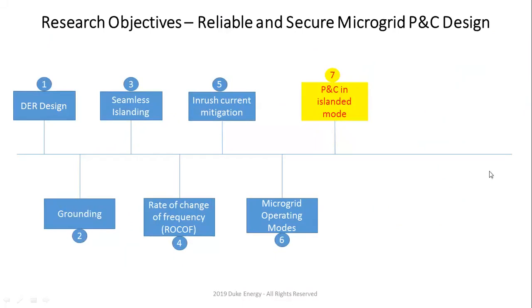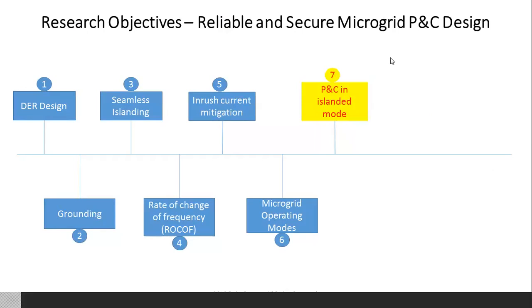We also have protection and control in island mode, which is probably one of the most challenging topics because inverter-based DERs do not produce a whole lot of fault current. Sometimes those fault currents can be within the range of high load currents, similar to the sub-transmission system when you have a long line and a fault all the way at the back of the feeder. How do you discriminate between low fault currents and high loading?